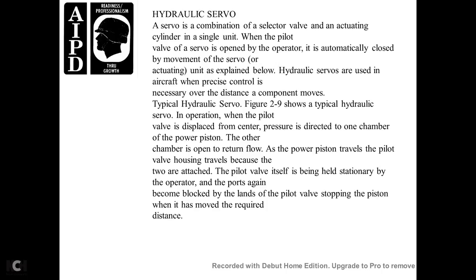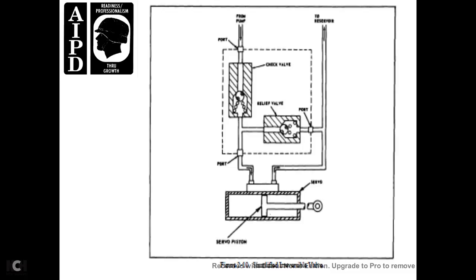In operation, with the pilot valve displaced from center, pressure is directed to one chamber of the power piston; the other chamber is open to return flow. The power piston travels, carrying the pilot valve housing with it because the two are attached. The pilot valve itself is held stationary by the operator. The ports become blocked by the lands of the pilot valve, stopping the motion when the piston has moved the required distance.